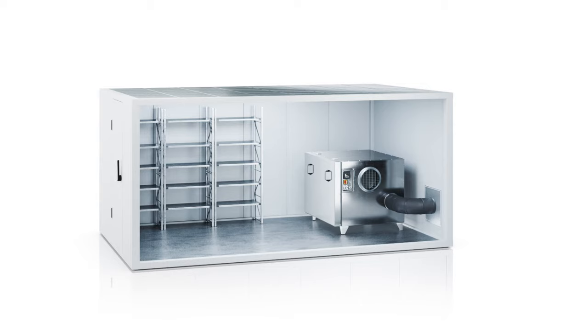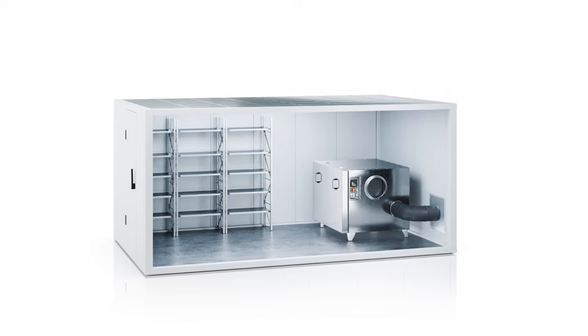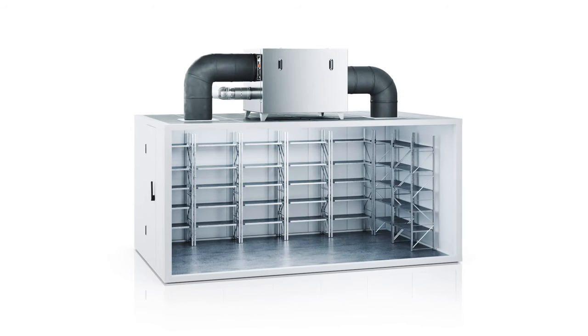Since the difference between indoor and outdoor air temperatures is usually substantial, it makes sense to install the adsorption dryer directly in the cold room. This helps avoid heat-related power losses. If the required space is not available in the cold store, the Condair Freezer featuring a special 100-millimeter-thick insulation can also be used outside the cold store.